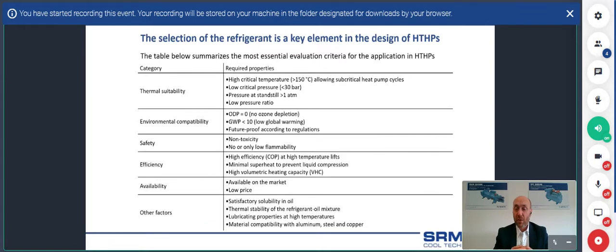The pressure at standstill is also very important, because normally it is necessary that at 20 degrees C, the common ambient temperature, the pressure in the system should be above the ambient pressure, so higher than 1 atmosphere or 1 bar. This is necessary to prevent leakage from the ambient into the system during standstill, which could happen if the pressure were lower than the ambient pressure. A low pressure ratio is also important in the selection of the refrigerant, because a low pressure ratio gives higher efficiency of the system.